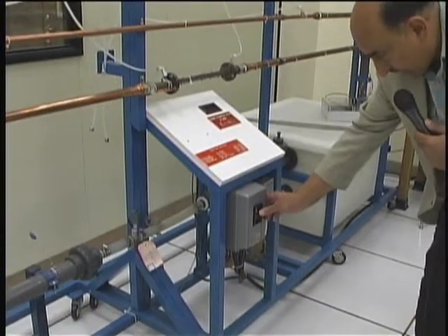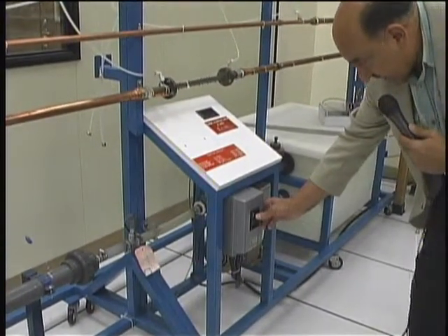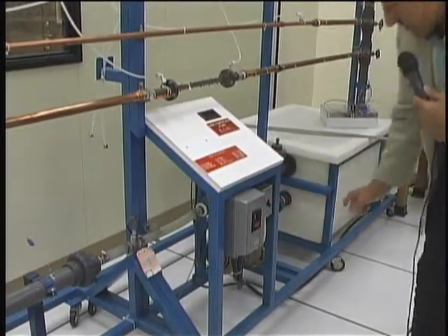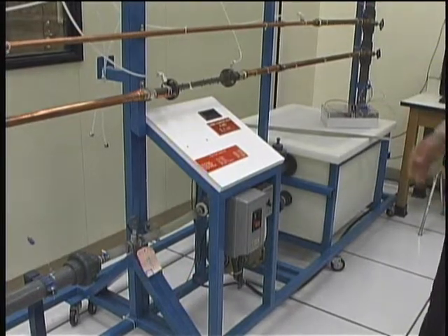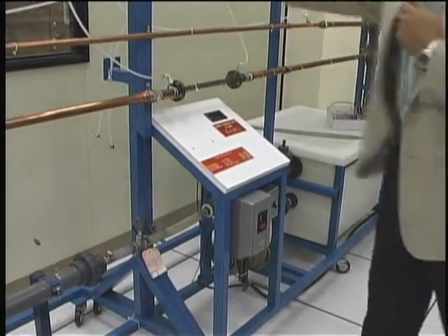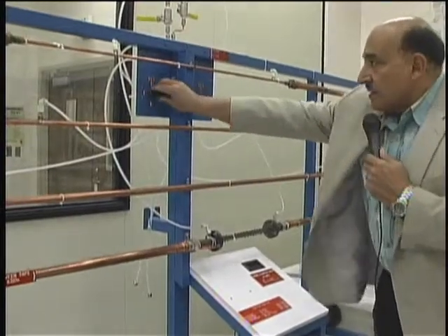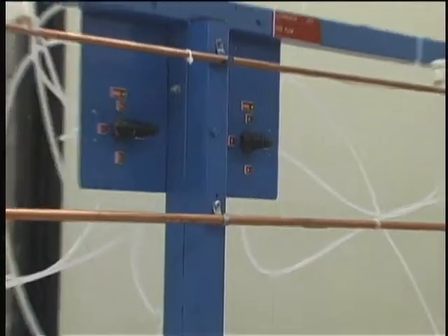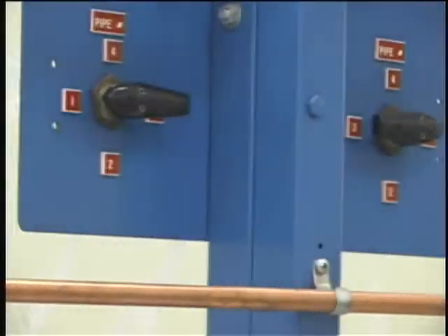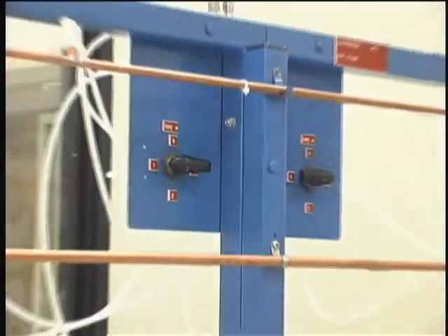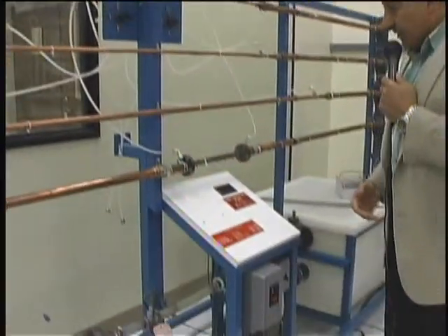And then you're going to turn on the pump by pushing the start button at the bottom here. So it's noisy already. So now we have full flow for pipe number 1 right here. It takes maybe a minute or two to go through. So the flow is being established. Now I'm ready to do some measurements.